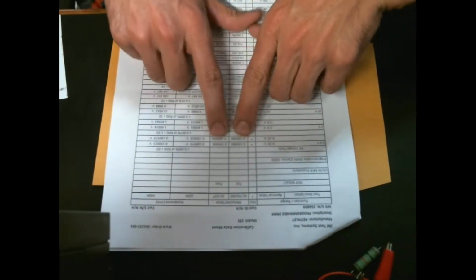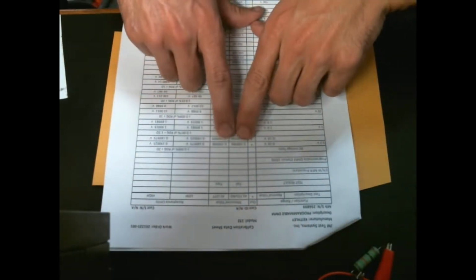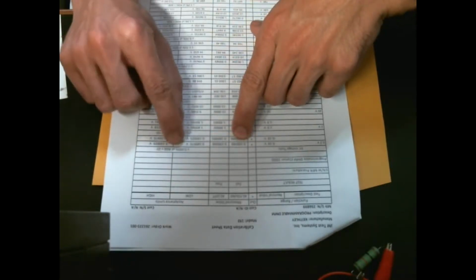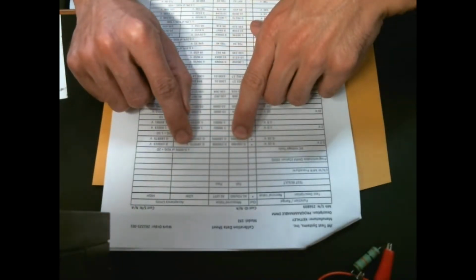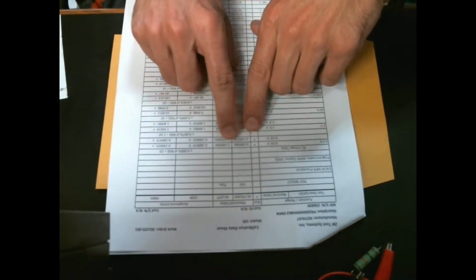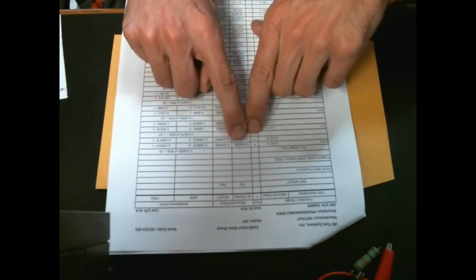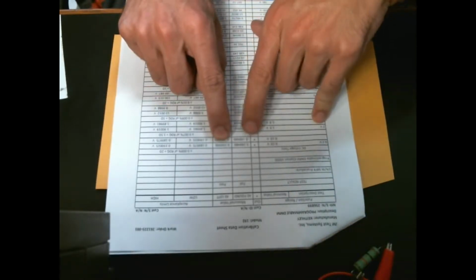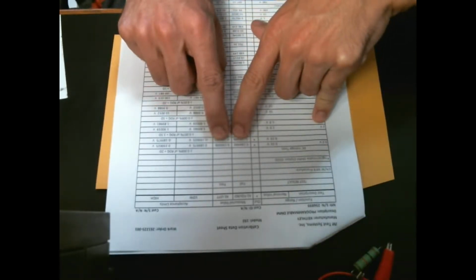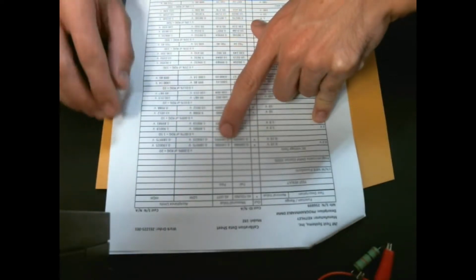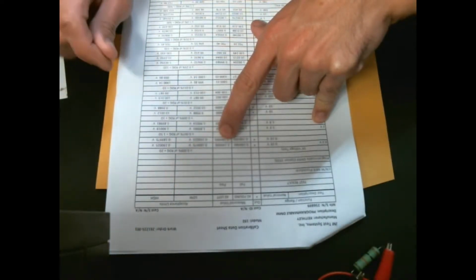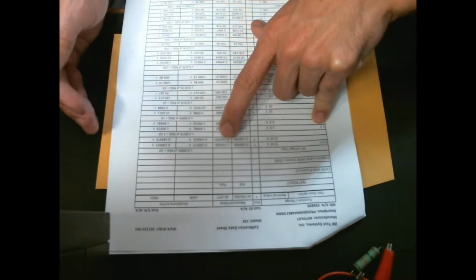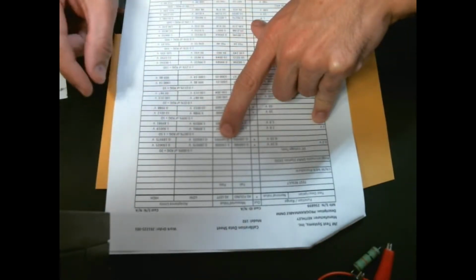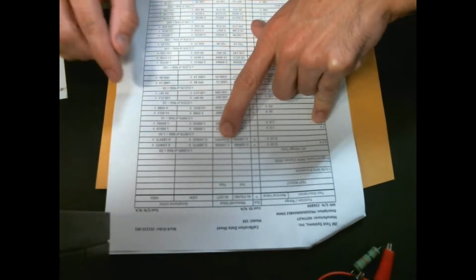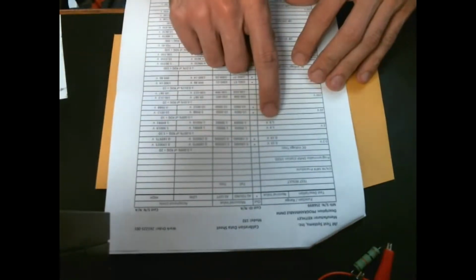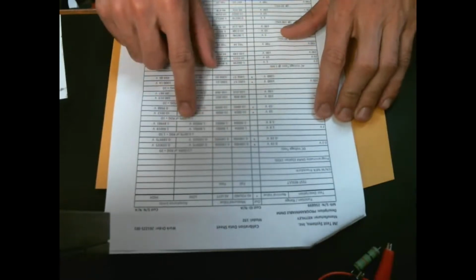But as you can see, we failed because we were quite a bit out for the accuracy rating that the reading was supposed to be. And they adjusted it. They actually only adjusted it about 0.00155 and a little bit volts. So it sounds really, really small, but whenever you're getting into these 6.5 digit resolutions, really, really small can become really, really big very quickly. 2 volts, the 2 volt range was fine.